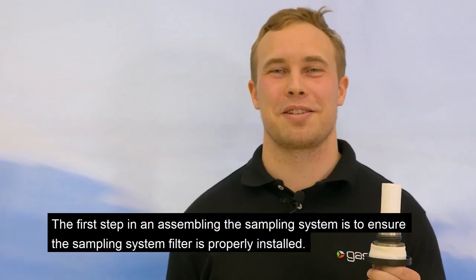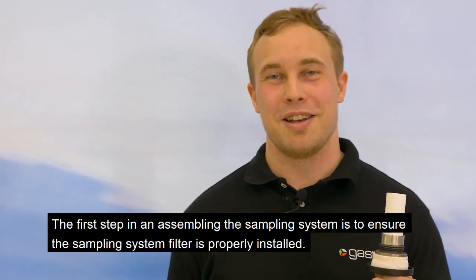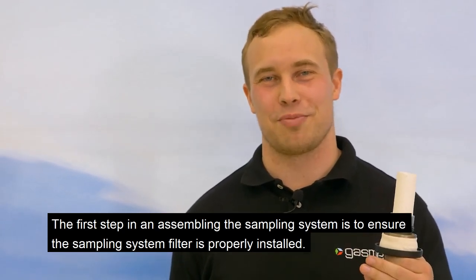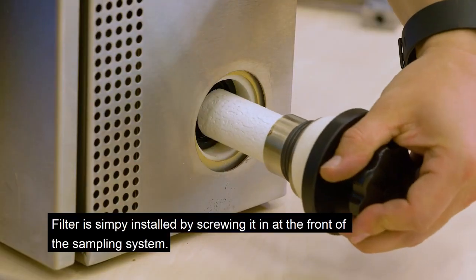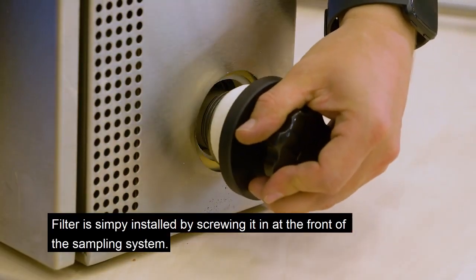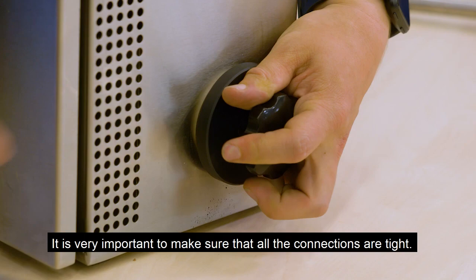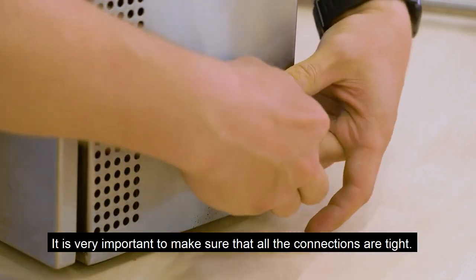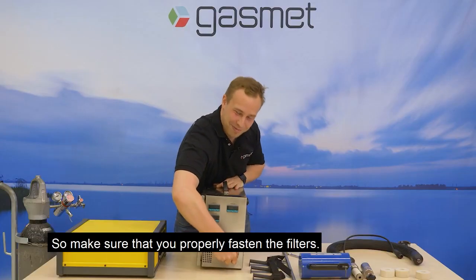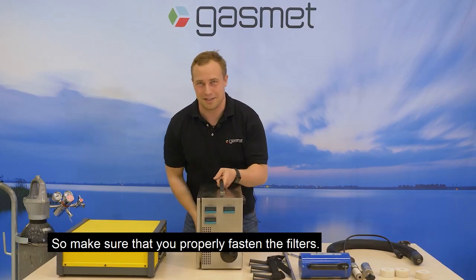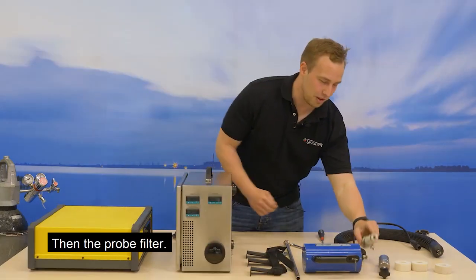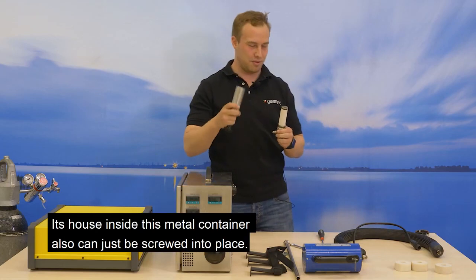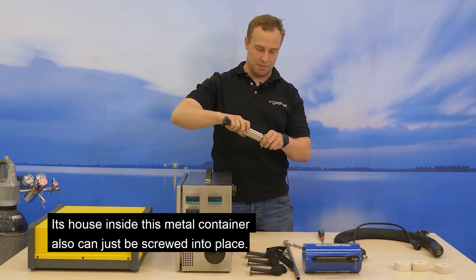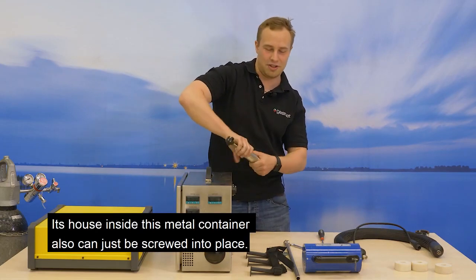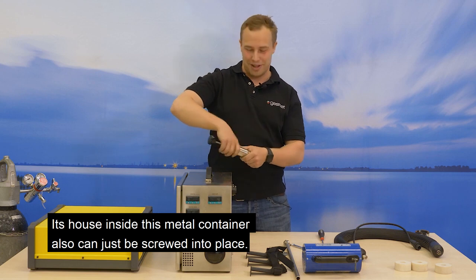The first step in assembling the sampling system is to ensure that the sampling system filter is properly installed. Filter is simply installed by screwing it in at the front of the sampling system. It is very important to make sure that all the connections are tight, so make sure you properly fasten the filters. Then the probe filter is housed inside this metal container, also can just be screwed into place.